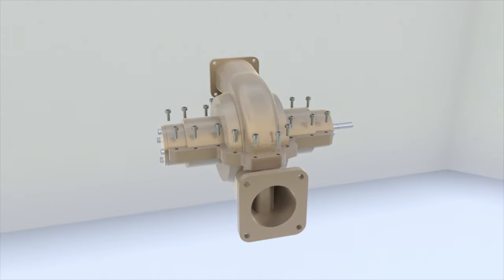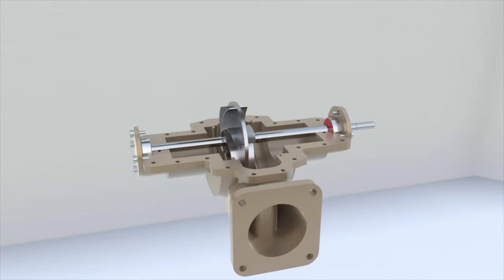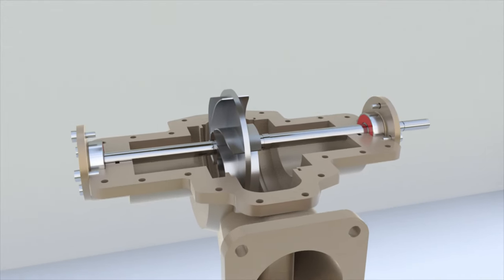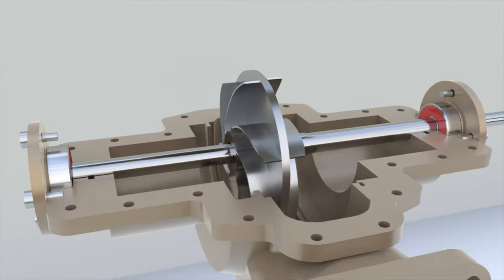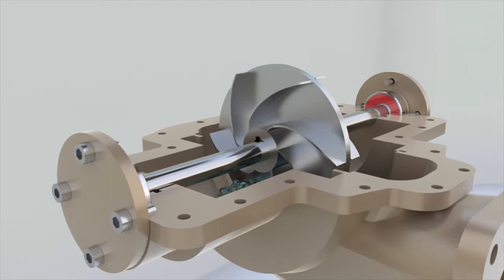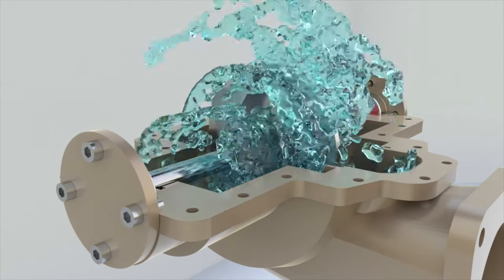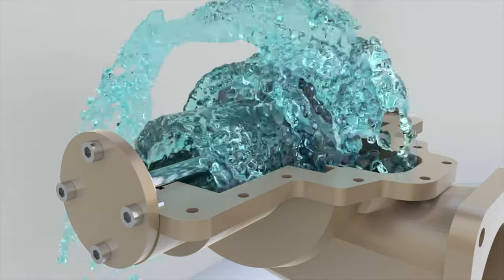A heavy impeller cannot be cantilevered. In this case, the shaft is mounted on bearings and the impeller is placed between them. This construction scheme is well suited for double suction impellers where the vanes are placed on both sides.